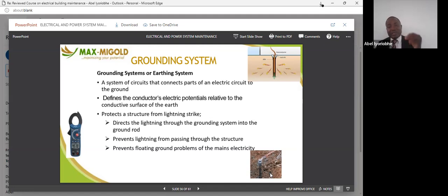it also increases your electricity bill at the end of the month. It costs more on your electricity bill because that fault current will be circulating around your installation. It will form part of the current that you consume, whereas you did not consume it. It's supposed to be a wasted current, fault current, a bad one. So if it's big enough, it will cause fire in the building. If there is a thunder strike, it will result in fire because you have a poor earthing system.